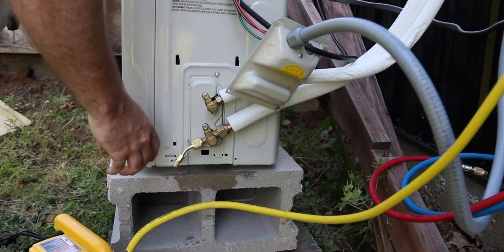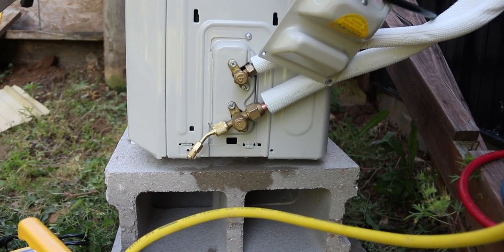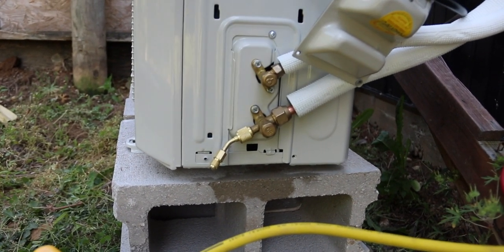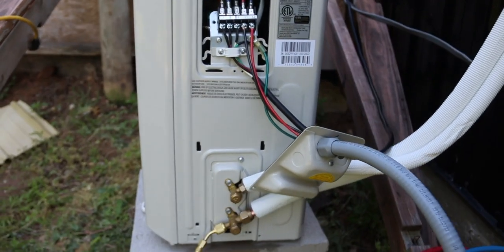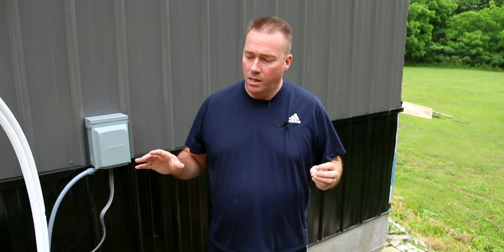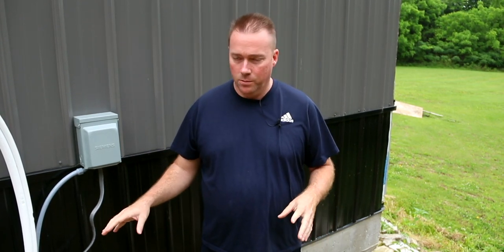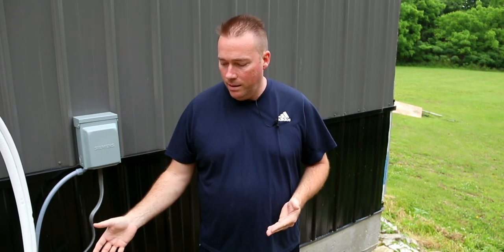This little piece here you're supposed to be able to take back off — it has a valve — but when I went to take it off, the valve was leaking a little bit of freon past it. Maybe we should have taken that off before we released the freon. These units can be really good. This one is 18,000 BTU — kind of overkill — and it's about $1,000 to $1,100 with everything. The Mr. Cool stuff was getting around $2,000 for the same unit. As we hooked this thing up, we realized all the connections were identical to Mr. Cool — on the head and on the outside unit. It looks the same, hooks up the same, all the connections are the same, the compressor looks the same. I'm thinking it's probably the same unit with two different companies' names on it.